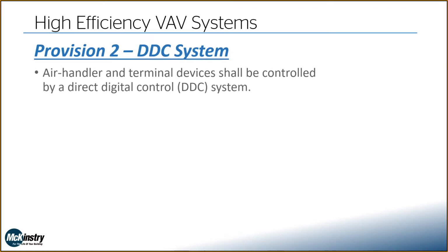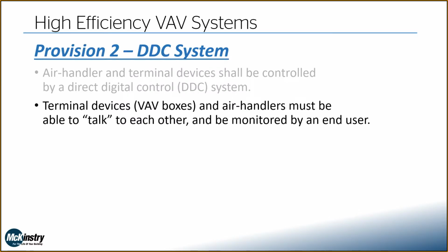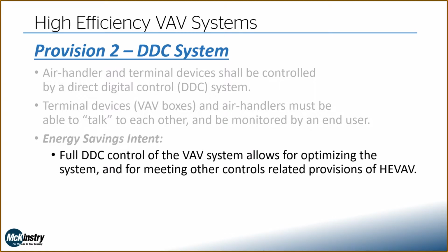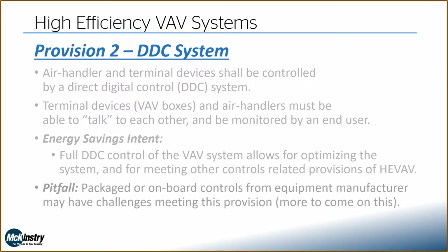The second one, DDC system. Your air handlers and your terminal devices, your VAV boxes, shall be controlled by a direct digital control system. Additionally, your terminal devices and your air handlers have to be able to talk to each other and be monitored by your end user. The intent here is if we have full DDC control of that system, it allows for better optimization of the system. If we can do custom sequences, which you're going to see are pretty much a necessity to meet some of the other provisions, having that DDC control gives you that capability.